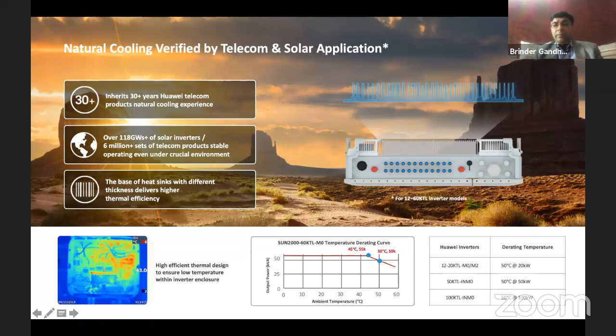And with the new 100 kilowatt inverters which we have launched, we have improved the cooling system, and we have brought in an innovative heat exchange for complete air circulation for cooling fins. So this is used for cooling fins circulation, not inside the inverter circulation. This is a highly reliable, innovative product, using a self-developed chipset for the fans, and it is a joint innovation between Huawei and another company. This fan has a unique feature: it starts in a reverse direction for a couple of minutes and then goes back to normal working, and it throws out all the dust or any other particles in the reverse direction to clean itself. We have tested this solution completely, and we expect a 25 year lifespan for the fans.